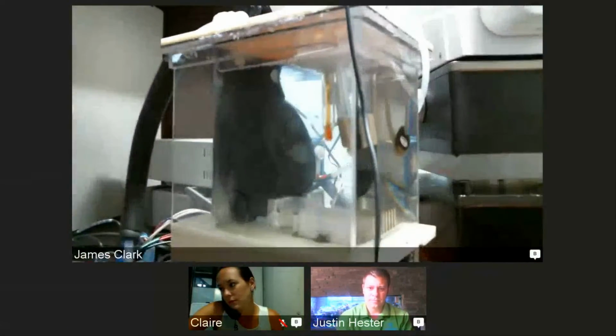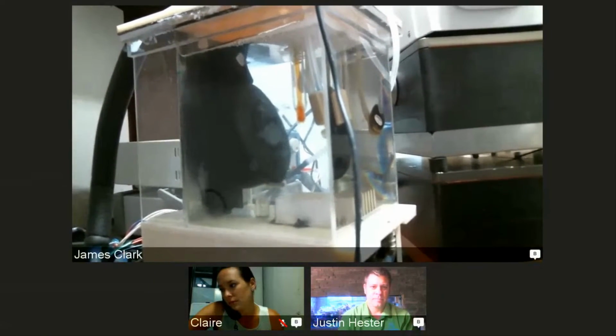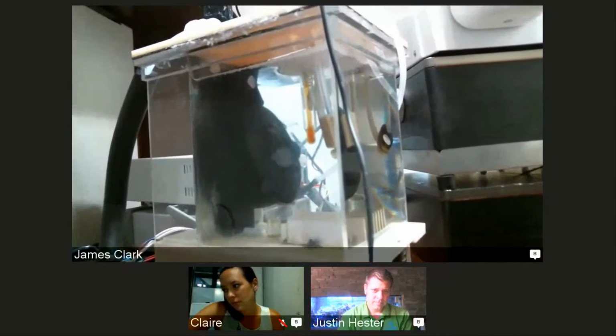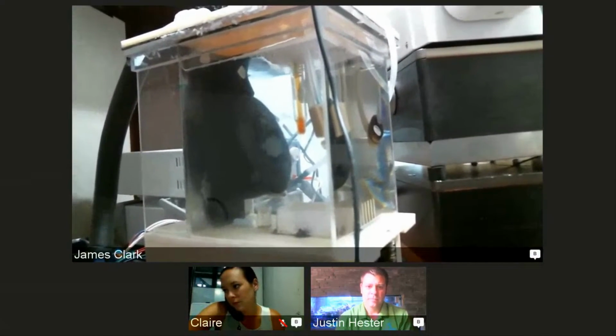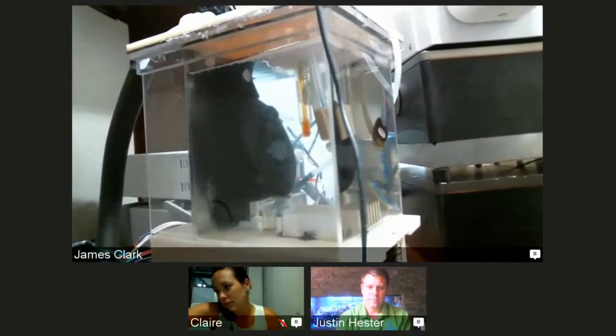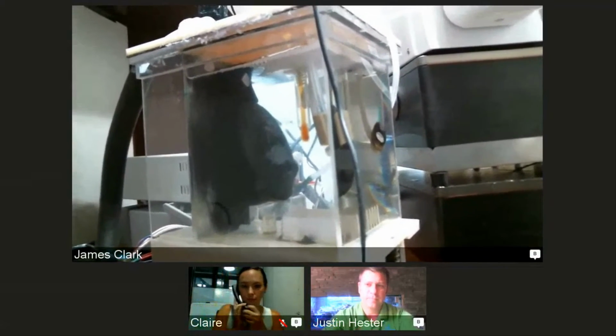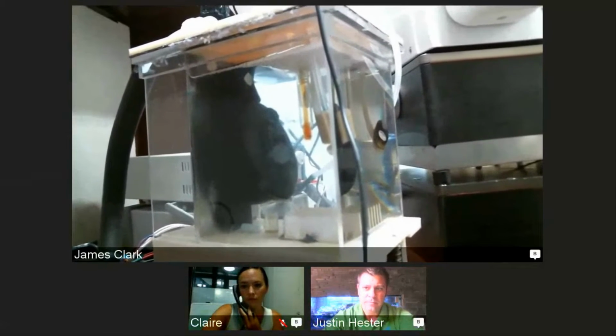You can see the Mindstream sitting in the background right now. It's not doing a measurement cycle at the moment, but it's always keeping the disc in motion so that it accomplishes two things. It keeps the water fresh underneath where the sensors are. If it were to sit still for the 15-minute intervals between measurements, you wouldn't have a fresh sample of water underneath it.